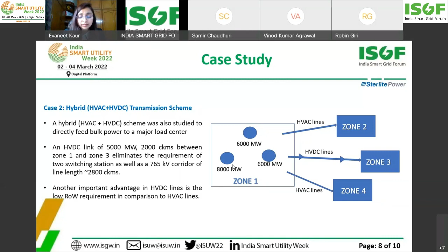Even though the HVAC scheme is cost effective, the hybrid scheme offers far more advantages, such as bulk power is injected into a single node and the same is evacuated to distant load centers through a dedicated long distance HVDC link, eliminating the need for multiple switching stations that we require in HVAC transmission lines. It also reduces ROW requirement, which has a time and cost impact on the project. It also improves system security in terms of angle and voltage stability. The reactive power requirement would also be lesser with an HVDC link.